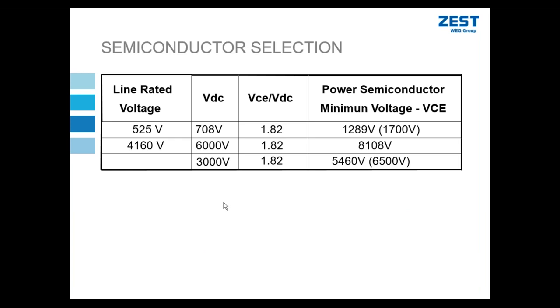So just to get back to the rating of the IGBTs, I said that those IGBTs are rated for 6.5 kV. Let's look at some general design principles when selecting a voltage rating for an IGBT for your device. In low voltage VSDs, for example a 500 volt VSD, the DC link could be up to 1.41 times that, the square root of 2 times my line voltage. But normally it sits at an average of about 1.35 times my line voltage. So in this case, my DC link could be as high as 708 volts.